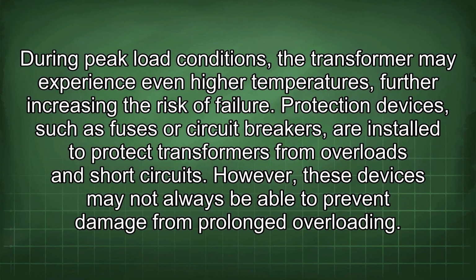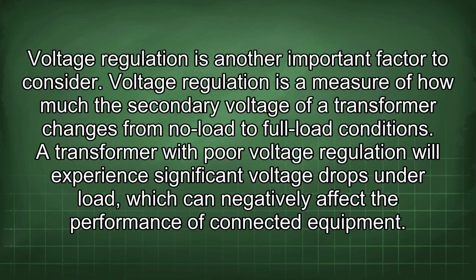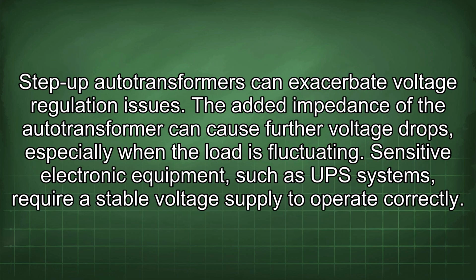Protection devices, such as fuses or circuit breakers, are installed to protect transformers from overloads and short circuits. However, these devices may not always be able to prevent damage from prolonged overloading. Voltage regulation is another important factor to consider. Voltage regulation is a measure of how much the secondary voltage of a transformer changes from no load to full load conditions. A transformer with poor voltage regulation will experience significant voltage drops under load, which can negatively affect the performance of connected equipment. Step-up autotransformers can exacerbate voltage regulation issues. The added impedance of the autotransformer can cause further voltage drops, especially when the load is fluctuating.